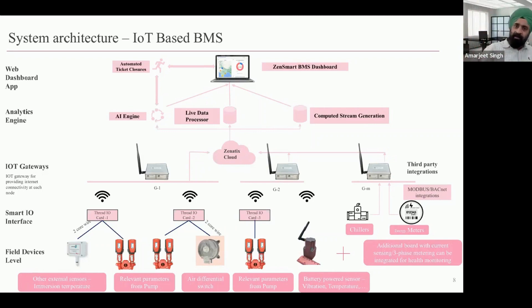Once you have all of this data, you put it to the best possible use. You are now collecting data every minute — storage is cheap, compute is cheap. You process this data through AI-based algorithms and create automated tickets. People don't need to manually infer data points; automated algorithms infer them and keep improving as they get more data. These tickets will have actionable insights — rather than just saying there is low cooling in an area, a ticket may say there is low cooling because the air filter is blocked, or the valve is stuck, or the VFD is stuck at 30 Hz. These systems analyze data across multiple subsystems to create actionable insights.